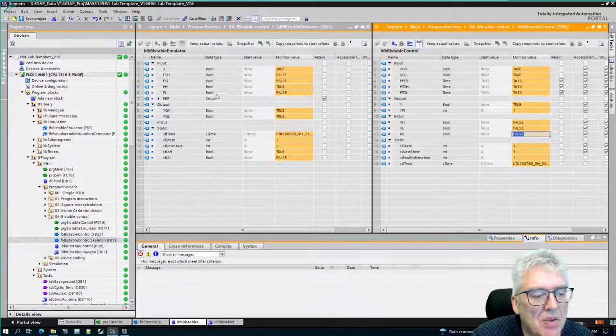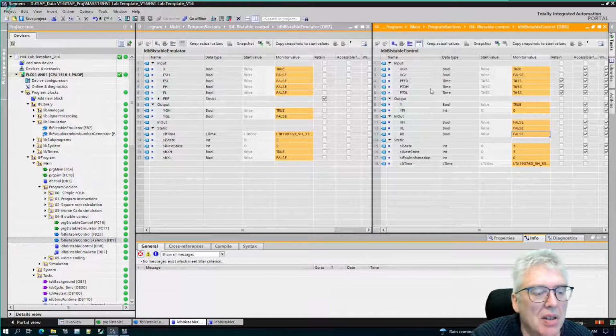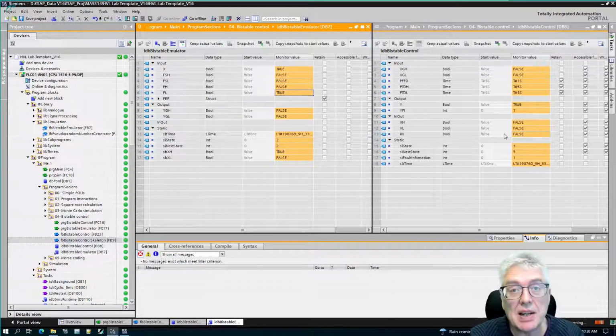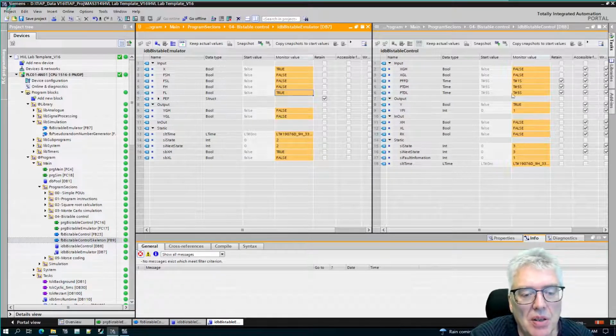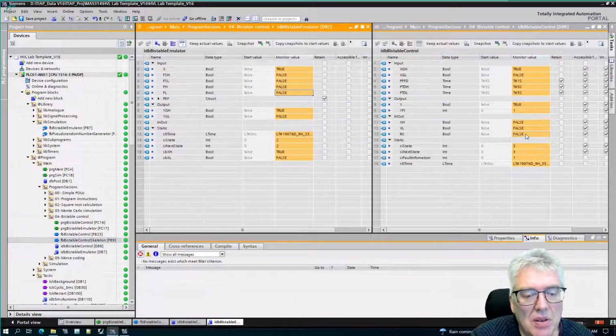And I can try to reset it. Just reset, because the feedback is false. So now I'm just going to say, okay, both feedbacks are back to normal. Reset the error. Fine. So I can also remove both my feedbacks. Now I have no feedback. That's a legal one, because it can be in transit. Both feedbacks high, then you have a short circuit or something on the feedback, or there's something wrong on it. So I got that one, can't reset it because the error is still there. And then I remove my go slow, and I can see I can reset it.